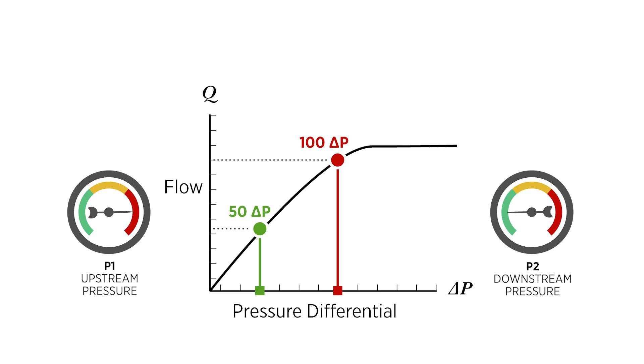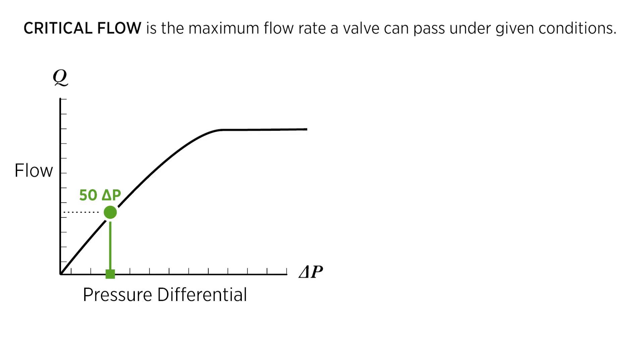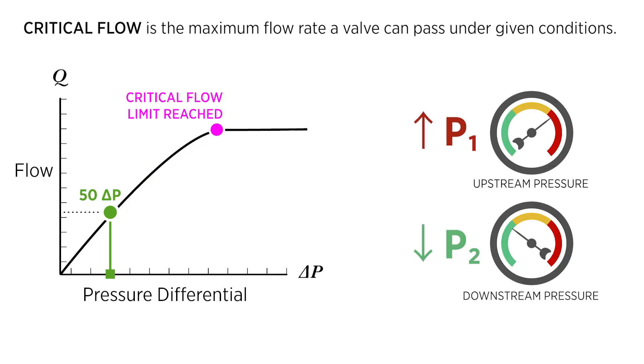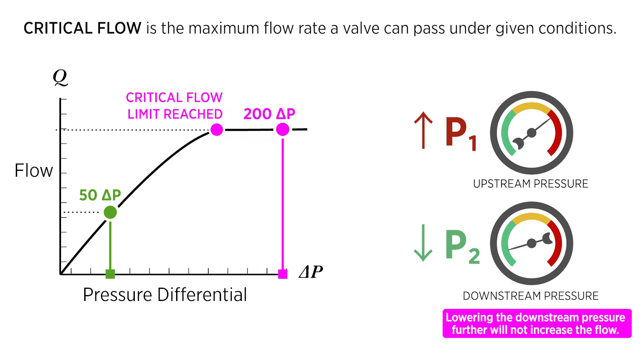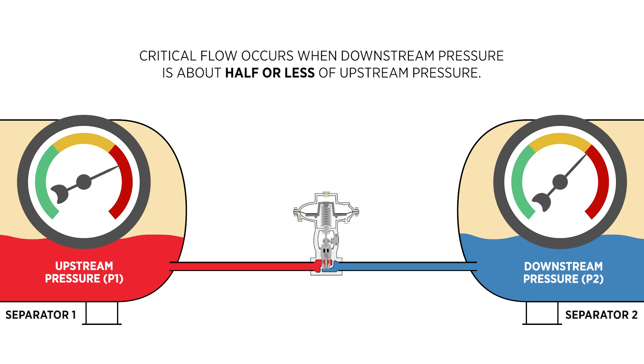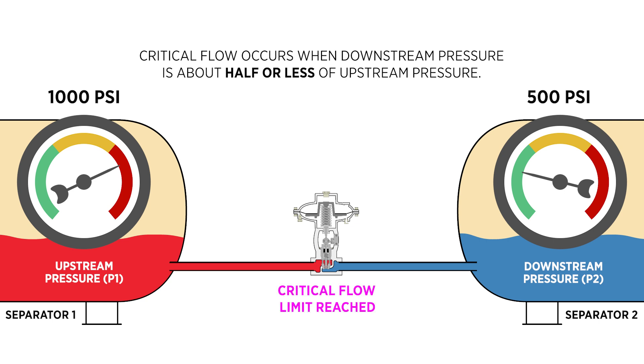You can raise the flow by either increasing upstream pressure or lowering downstream pressure to a certain point. Critical flow is the maximum flow rate a valve can pass under given conditions. Once the limit is reached, lowering the downstream pressure further will not increase the flow. Critical flow occurs when downstream pressure is about half or less of upstream pressure. For example, if a valve has 1000 psi upstream and 500 psi downstream, the valve has reached critical flow, and reducing downstream pressure further won't change the flow rate.